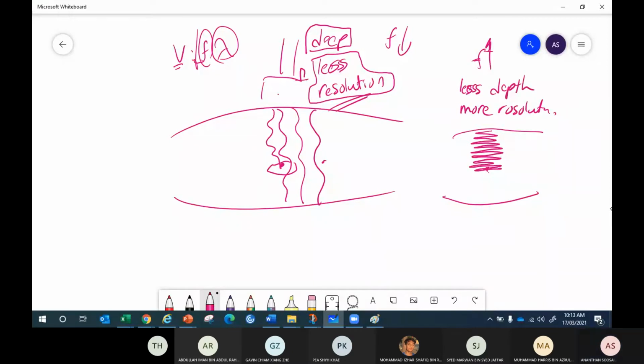That's the factor of frequency. So the doctor will decide whether to use high frequency or low frequency. If you want to check an organ which is quite close to the skin, maybe you go for high frequency to have a better resolution. And of course, you can also change the intensity. High intensity, the amplitude is going to be big, more energy, you can go deep. If you want to go deep and have more resolution, use high frequency and high intensity, but it is dangerous because it can heat up the tissue.